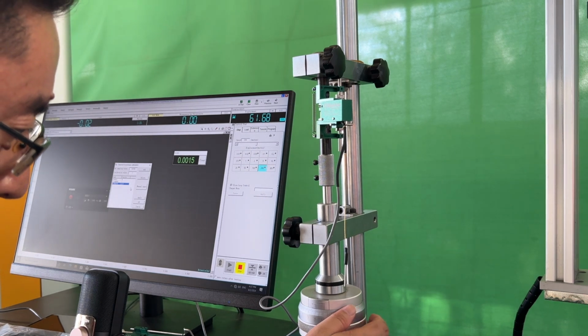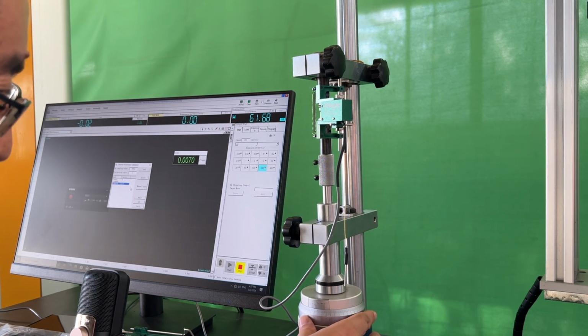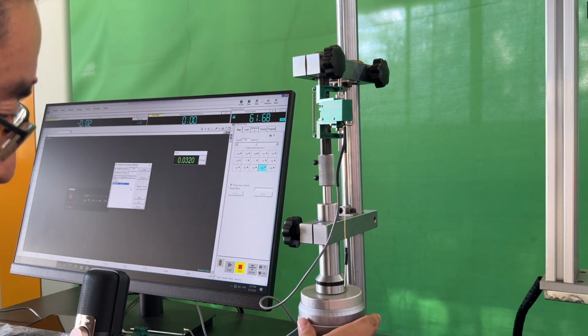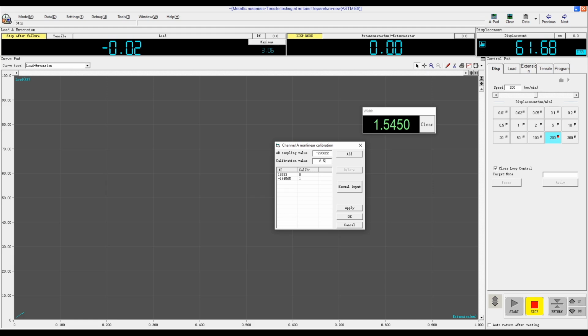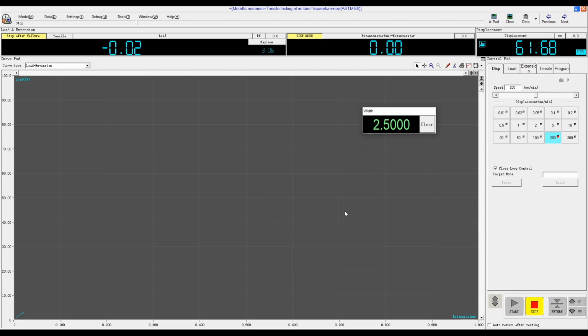For the first point, we will calibrate at 1 millimeter. Now that it is at 1 millimeter, click Add, and we will move to the next point, 2.5 millimeters. At 2.5 millimeters, click Add, then click Apply, and finally click OK. After that, we can check for accuracy. 1 millimeter, 0.5 millimeters, 0 millimeters. This completes the calibration procedure.